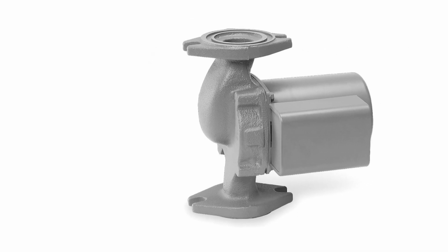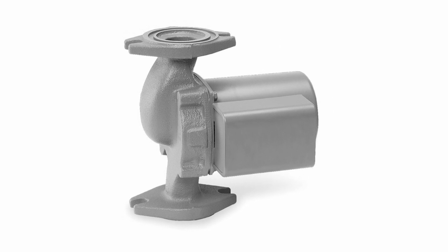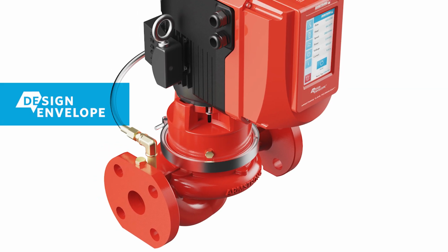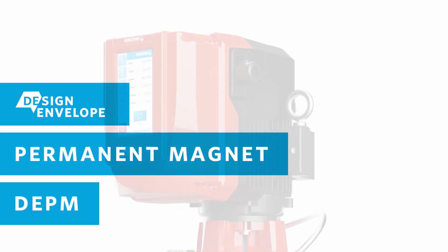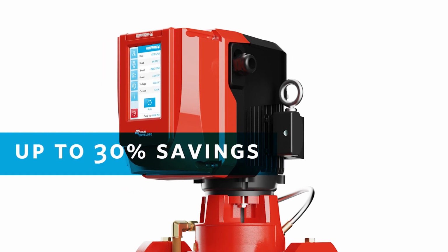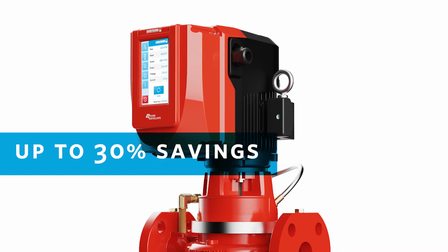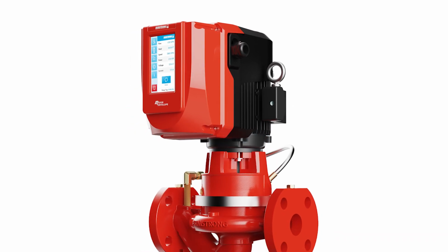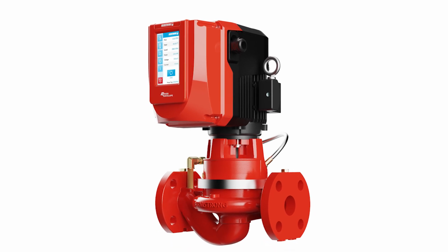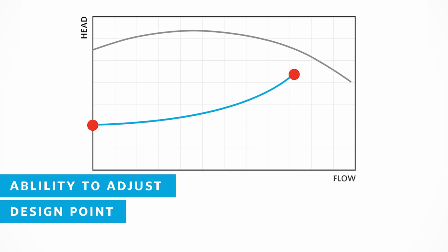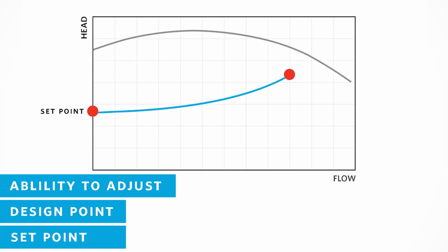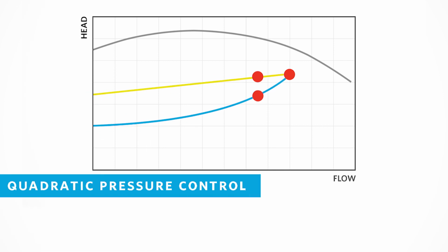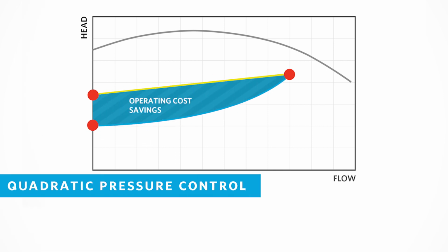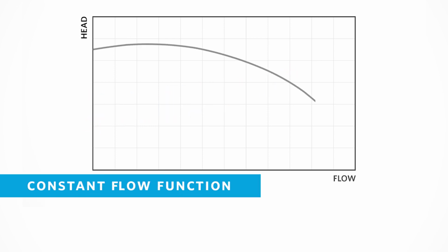Compared to conventional ECM circulators or pumps with loose drives and standard induction motors, Armstrong Design Envelope Permanent Magnet Motor Pumps, or DEPM pumps, also provide up to 30% operating cost savings. These savings are the result of several design innovations that make Armstrong DEPM pumps clearly superior. These innovations include the ability to adjust both the design point and the set point based on the actual on-site conditions, a quadratic pressure control curve versus a linear pressure control curve, and a constant flow function for maintaining the desired flow rate in recirculation applications.